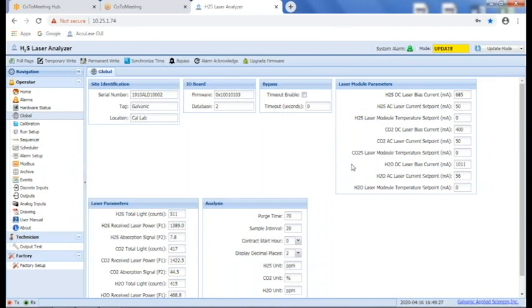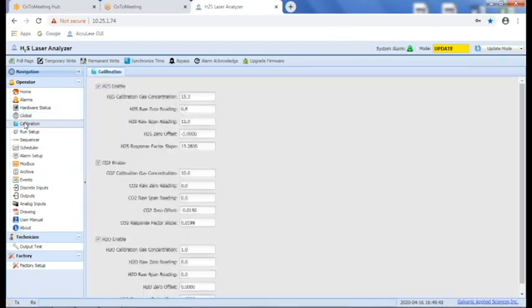For example, over here, you can see some of the parameters associated with the three different laser wavelengths that we're using. You can see how the drive currents can be set. Down here, we have things related to purge time, how often we want to sample the different gases. There's a calibration page that allows you to enter the concentration of the gases that you're measuring.